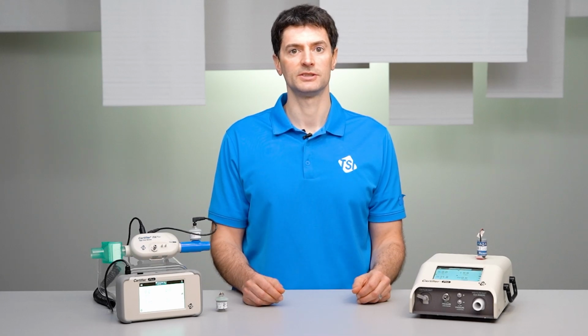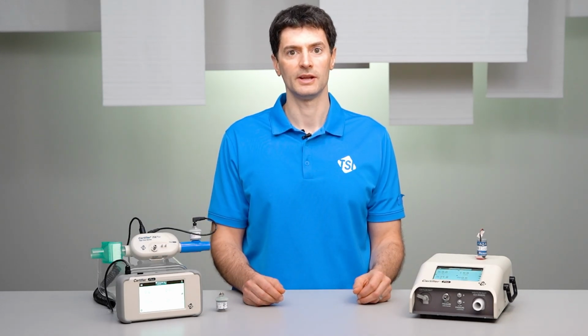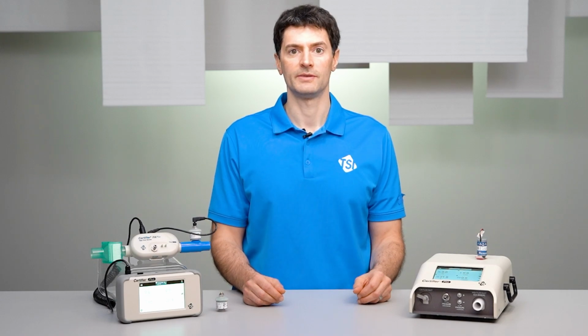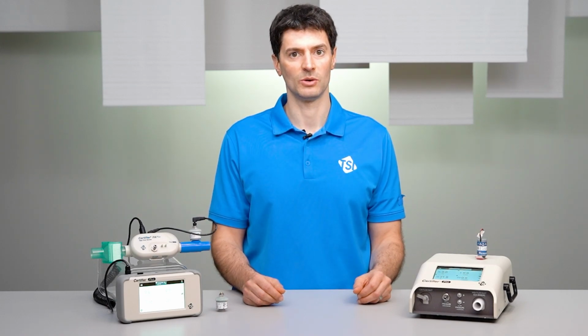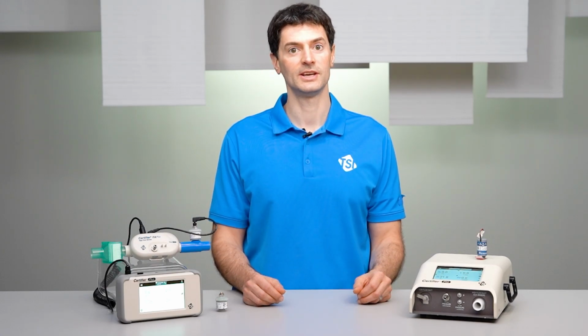If an oxygen sensor is installed in the instrument and is less than 6 months old when received by TSI, then TSI will calibrate the oxygen sensor. If the sensor is more than 6 months old, then TSI will replace it with a new sensor and then calibrate it.